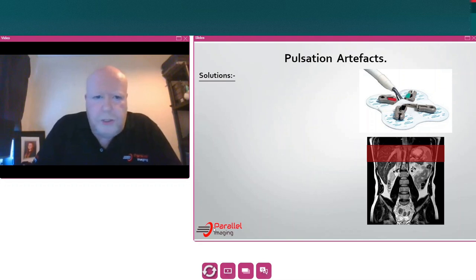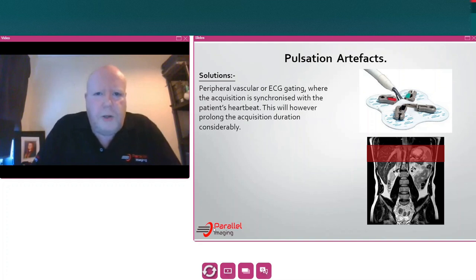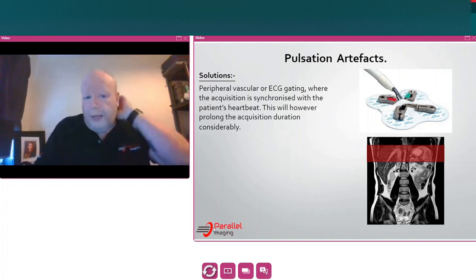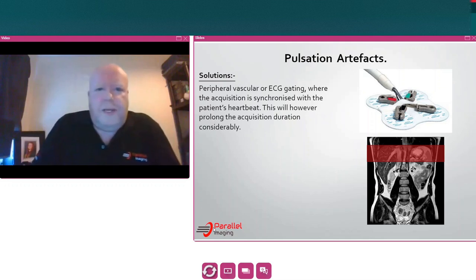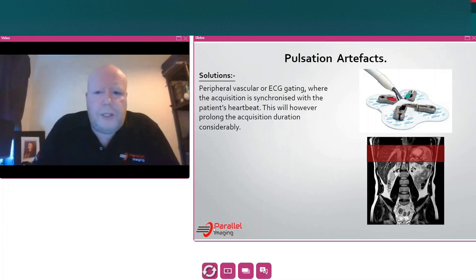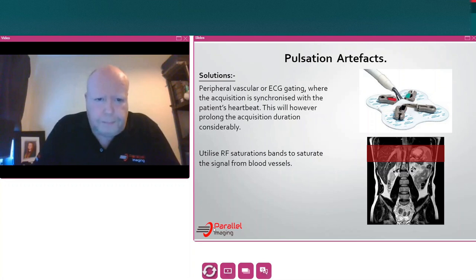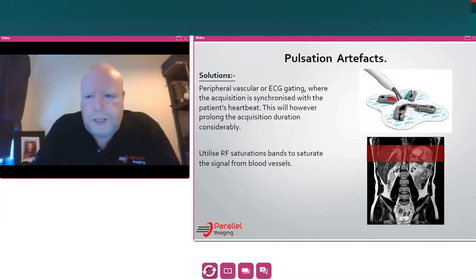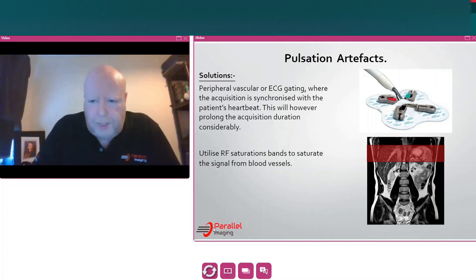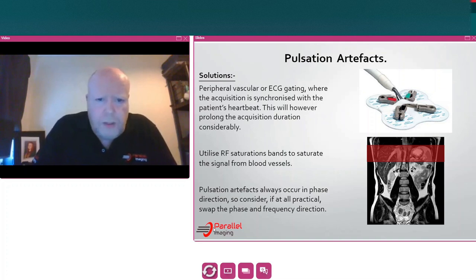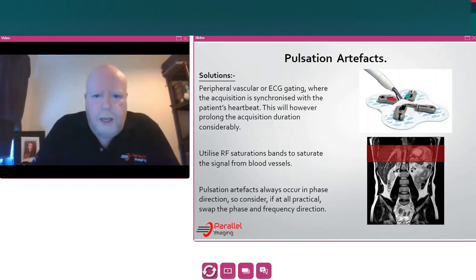Solutions for pulsation artefact include utilising peripheral vascular or ECG gating, where we synchronise the acquisition with the patient's heartbeat — though the downside is it will prolong acquisition considerably in some cases. Use RF saturation bands to saturate the signal from the blood vessels as blood comes into the field of view, which will reduce the pulsation artefact. Because pulsation artefacts always occur in the phase direction, if at all possible, consider swapping the phase and frequency direction.